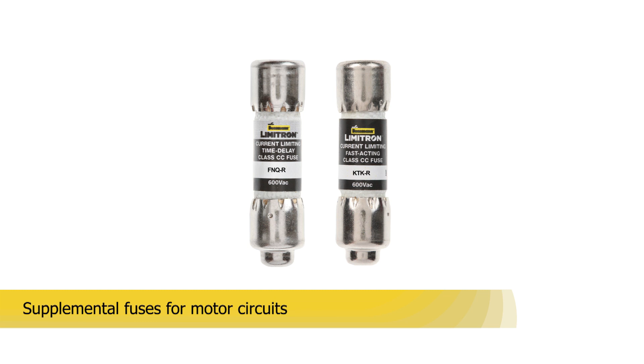In contrast to the branch circuit fuses, supplemental fuses and other application-limited overcurrent protective devices cannot be used in a building electrical system. These include supplemental fuses listed to UL 248, supplemental protectors, and motor circuit protectors. These devices are limited in their application and could cause a serious safety hazard if misapplied. These application-limited devices have limited agency listing and use, limited voltage ratings and interrupting ratings, and varying construction and performance characteristics. For these reasons, it is important to not let their lower price sway decision-making while sacrificing safety and performance.